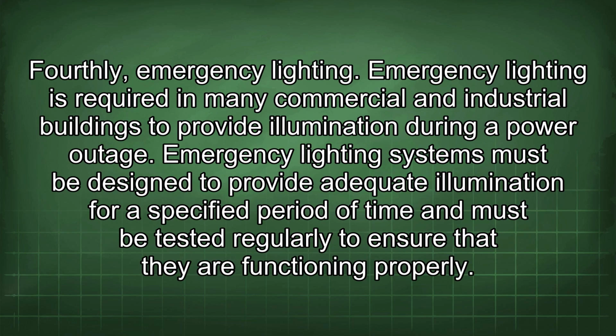Fourthly, emergency lighting. Emergency lighting is required in many commercial and industrial buildings to provide illumination during a power outage. Emergency lighting systems must be designed to provide adequate illumination for a specified period of time and must be tested regularly to ensure that they are functioning properly.